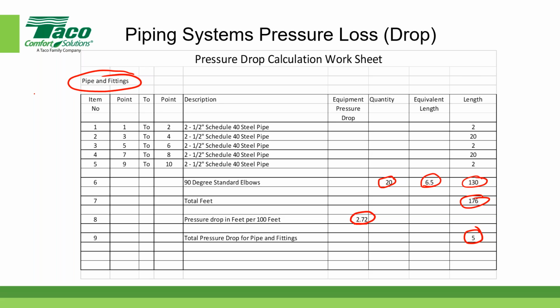We actually have two folks asking what the penalty of oversizing pipe is, or the consequences. What's the penalty for overestimating the pressure drop? Picking a diameter of 3-inch instead of 2.5, or 4-inch instead of 3. If you make the diameter too large, then your velocity gets quite low. Most of the time, in terms of HVAC systems, most people want to be in the range of roughly 6 to 10 feet per second.